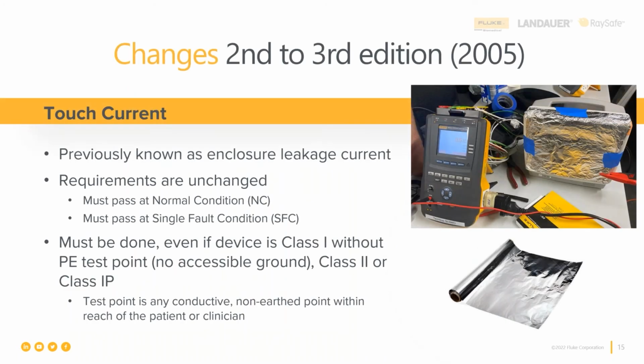Oh, well, let me first talk about a couple of things that changed from the second edition of the IEC 60601-1 to the third edition. We have a test called touch current. And touch current was previously known as enclosure or chassis leakage current. So if you've been around for a while, you may be familiar with the older names for this test, but all these names mean the same thing. It's called touch current now for a reason. The requirements are unchanged.